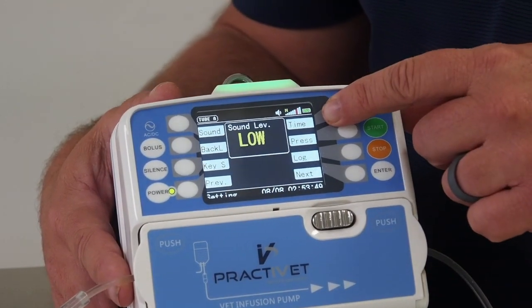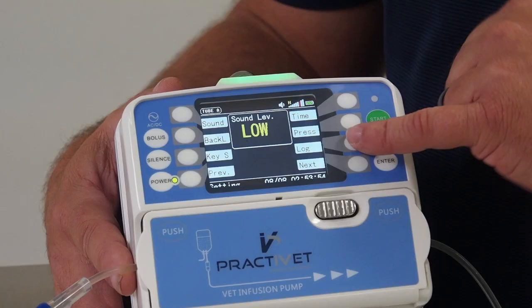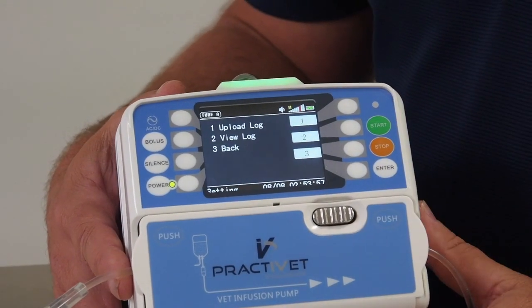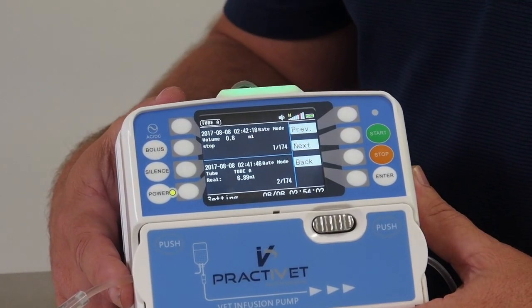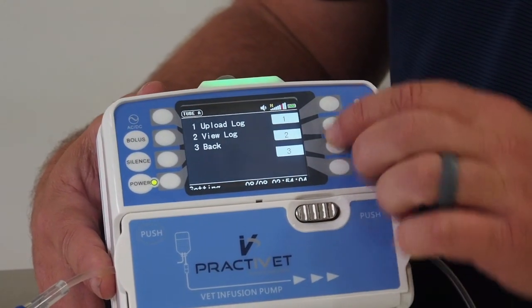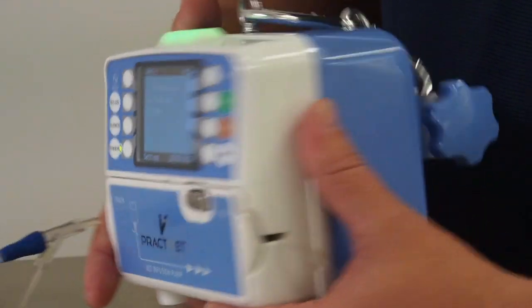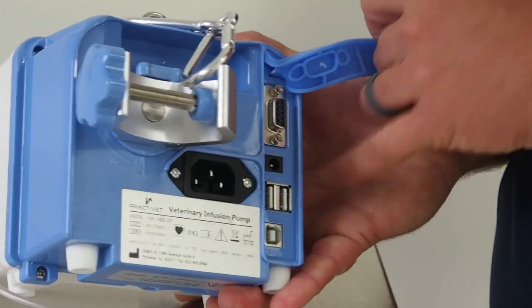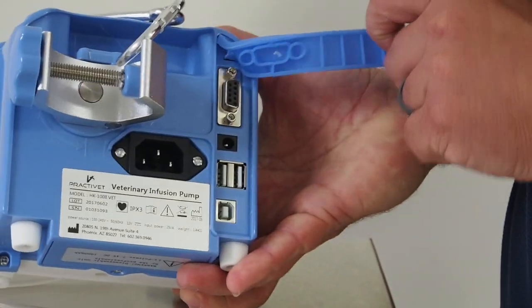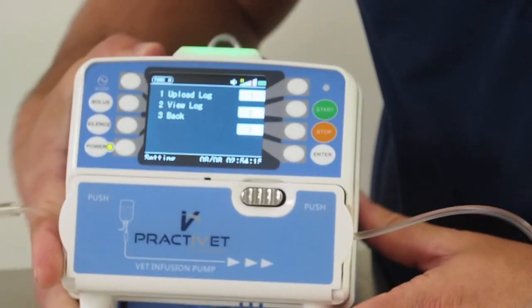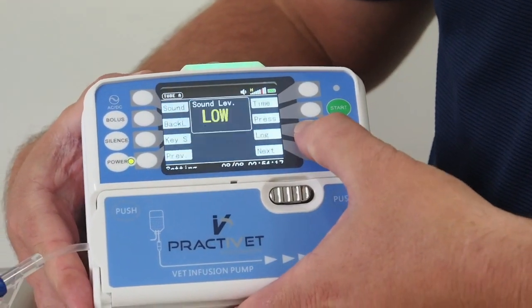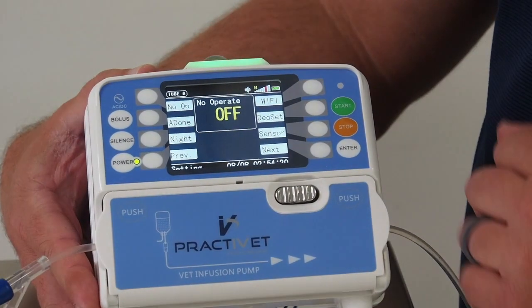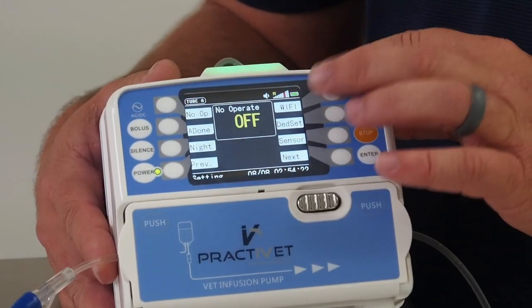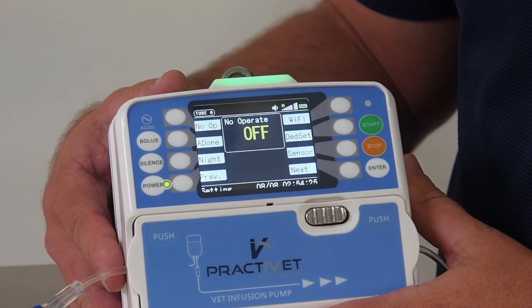I can adjust my time and date, which I recommend you doing when you get the pump in. And the reason that's important is because you can go into the log, the infusion log, and review the past 1,800 infusions. You can also download or upload that log to a jump drive in the back of the unit. Next, some other features. The pump is Wi-Fi, so you could turn the Wi-Fi on if you wanted to monitor it from a monitoring station.